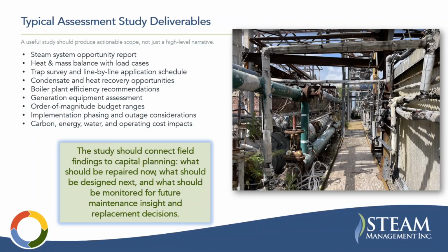I think a good assessment is going to have a heat and mass balance with load cases in many scenarios. You want a trap survey and line-by-line application schedule, condensate and heat recovery opportunities, boiler plant efficiency recommendations, generation equipment assessments, order of magnitude budget ranges, which is important, implementation phasing and outage considerations, and carbon, energy, water, and operating cost impacts. The study should connect field findings to capital planning: what should be repaired now, what should be designed next, and what should be monitored for future maintenance insight and replacement decisions.